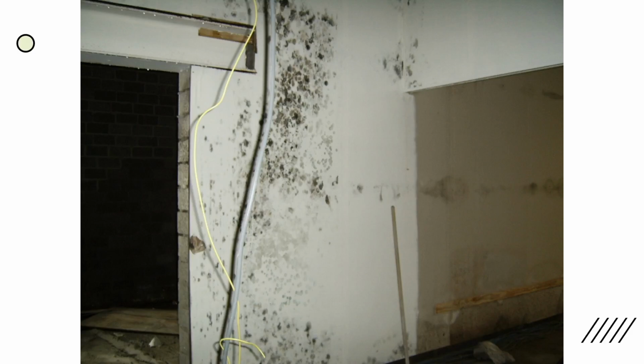You can see from this image here the mould that's appearing on the walls. Now, it's not just at the bottom, which would indicate a rising damp, and it's not so much mould at the top of the room, usually in the corners of the walls and the ceilings, where it's really bad ventilation, and that's a classic sign where there's either moisture ingressing through the brickwork from perhaps faulty guttering, leaking through the mortar gaps in the brickwork, and it's coming in, creating mould issues there. This is all over. This is an example of really, really poor ventilation, and a big issue with relative humidity.